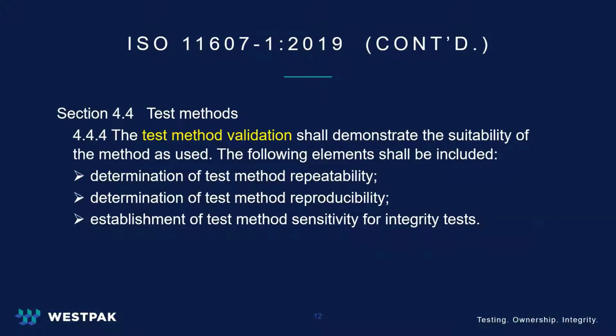Let's take a look at subsection 4.4.4 and dive deeper into the actual requirements of what a TMV shall provide. This section defines more clearly the specific requirements a TMV must be able to prove. The three key items that a validated test method must prove are that it must have a determination of test method repeatability, a determination of test method reproducibility, and an establishment of test method sensitivity for integrity tests, which can be considered the precision and bias.